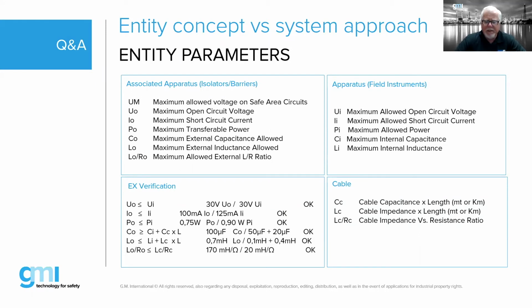There's going to be more energy stored the longer the length of cable. For example, you might see an installation where our loop drawing says we could only go 200 meters from our associated apparatus to the field device. If I'm going in to do an inspection on that, I want to make sure that you haven't gone 210 meters or 250 meters. You have stayed within that parameter, because if we cut the cable or something happens at that point, all of a sudden we've introduced more energy that will be above the minimum ignition energy amount that potentially could ignite the gas or vapor that's in that environment. So cable is a very important thing. It's very much overlooked, but it shouldn't be overlooked.